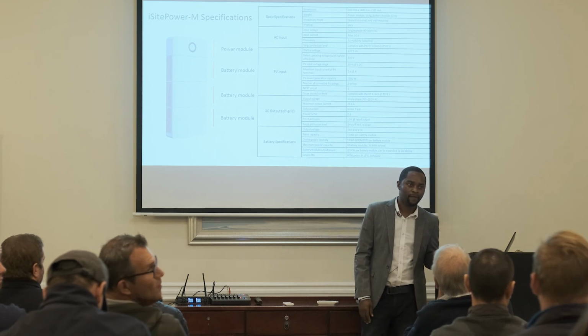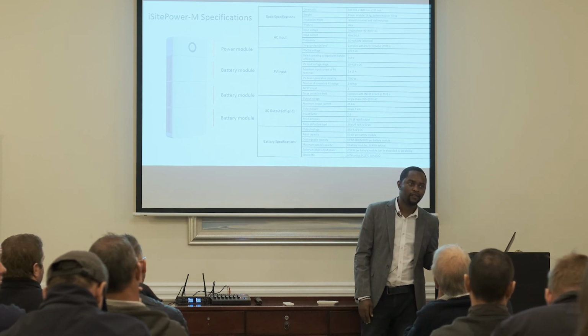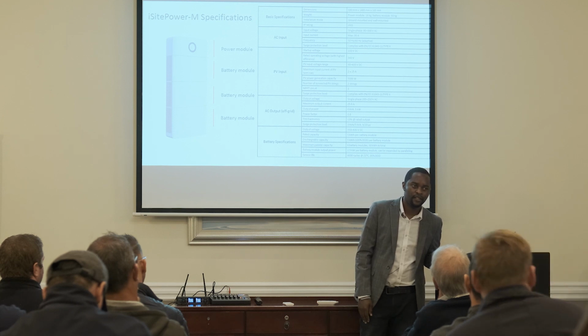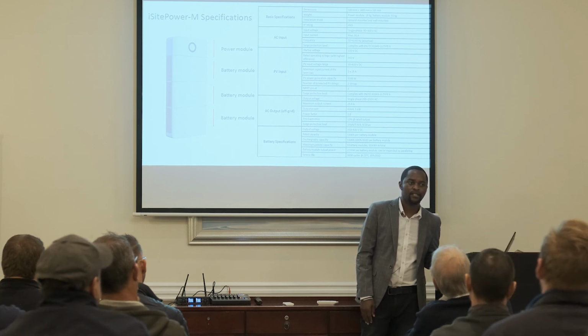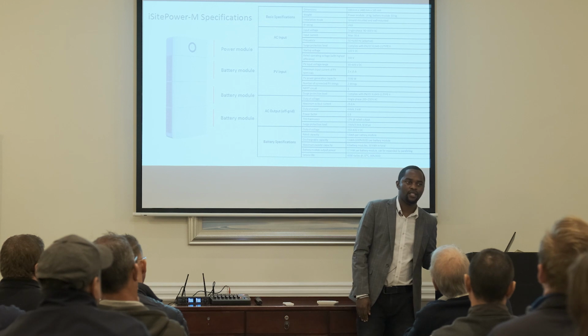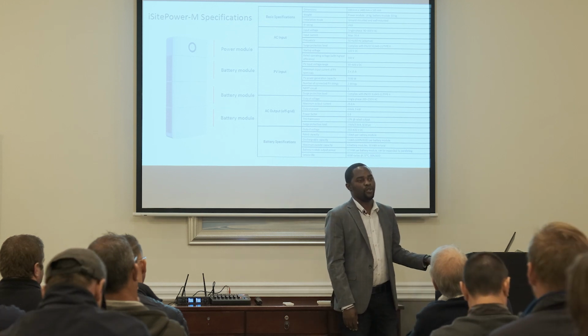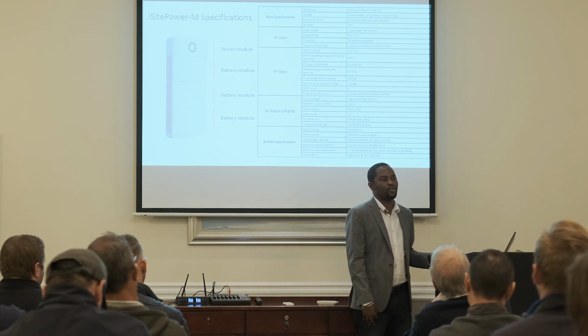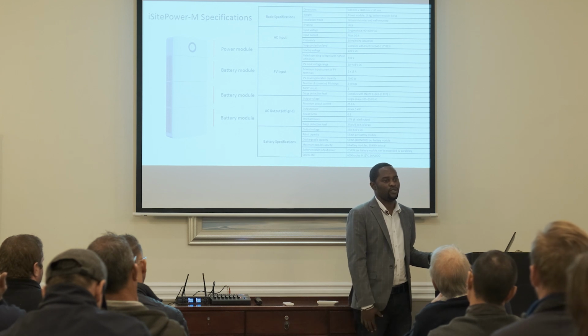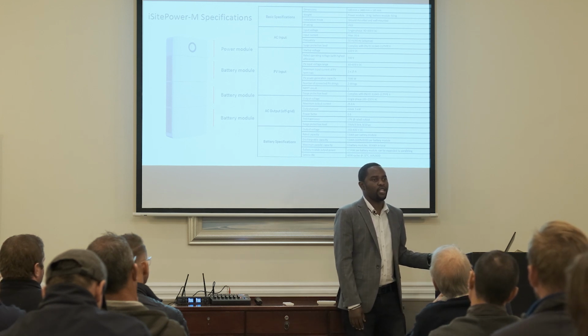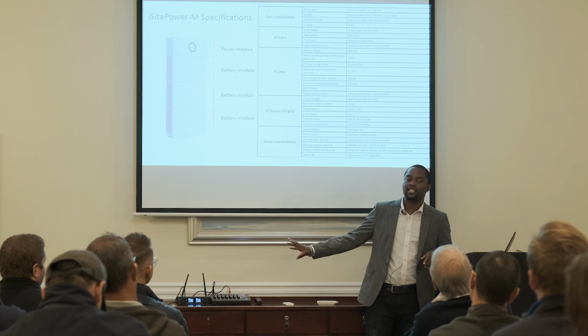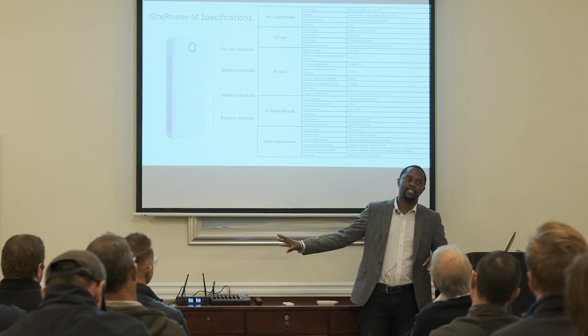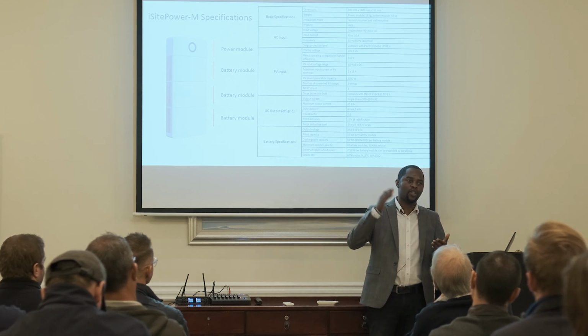Battery charges, are they built into the battery, into the power module? Come again? The charging for the battery, is it built into the power module or the battery module? It's built in the power module. So the charge is built in the power module. So the more battery modules you have, the slower the charge time. So the charge is determined by your inverter size. So this inverter is a 5 kilowatt inverter, and you can use all that to charge your batteries.